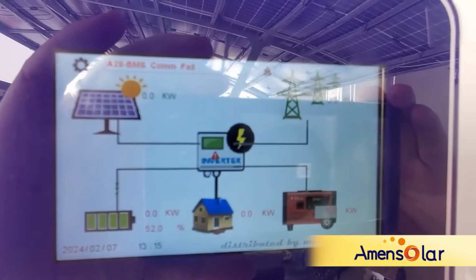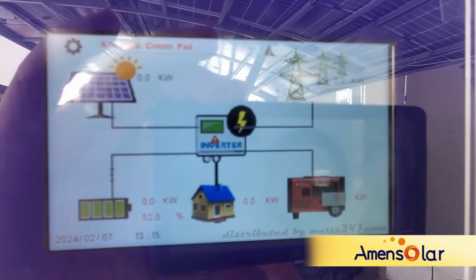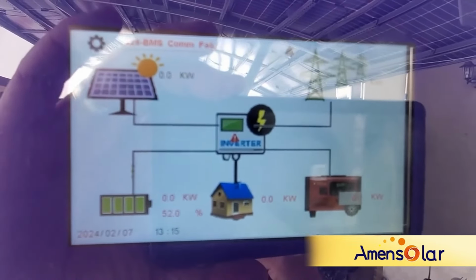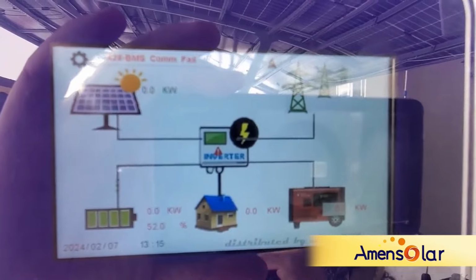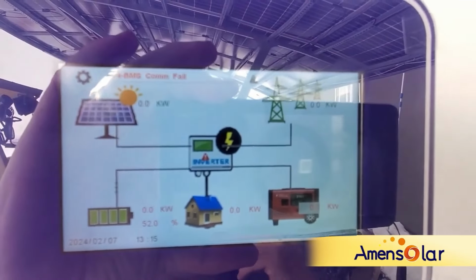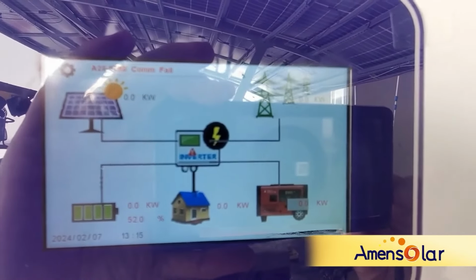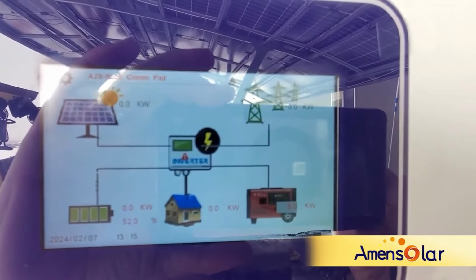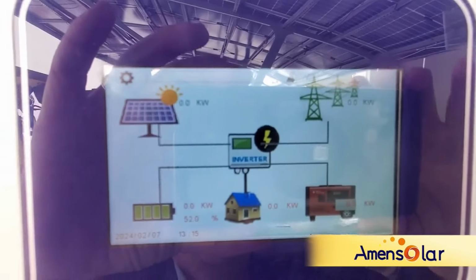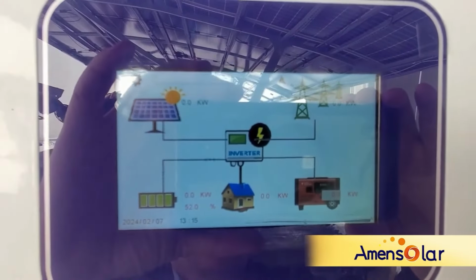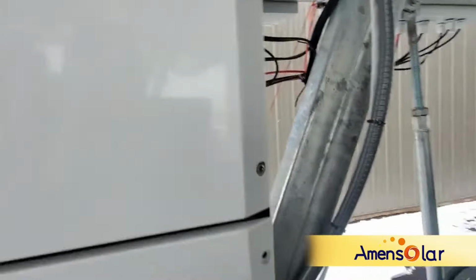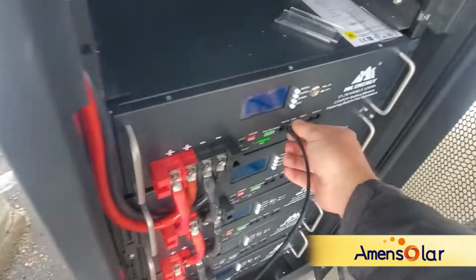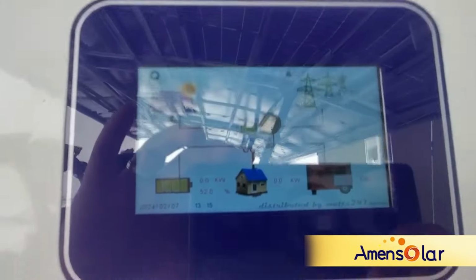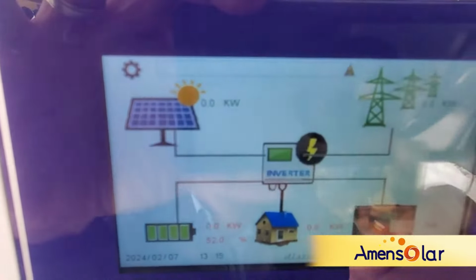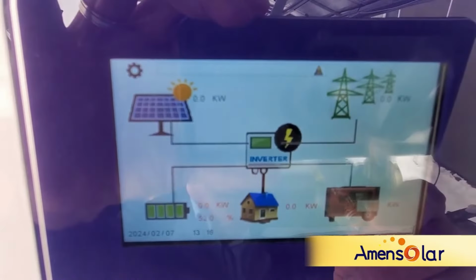Okay, it's telling us the BMS comms failed. Give it some time. And there, the BMS comms light has disappeared, so we know it's communicating. The way to test that, we can unplug this wire on the CAN bus, and within a few seconds we'll see it say BMS comms failed again.